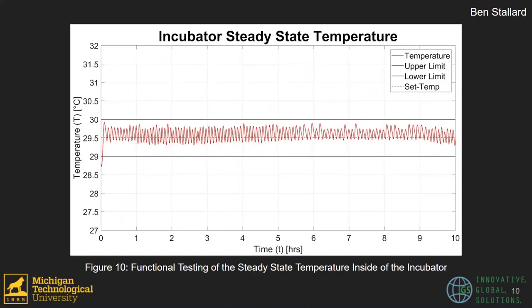And in this test, you can also see that throughout the entire length of the test, aside from when we first turned it on, the temperature of the incubator stayed within the required bounds and didn't even get particularly close to exceeding them.